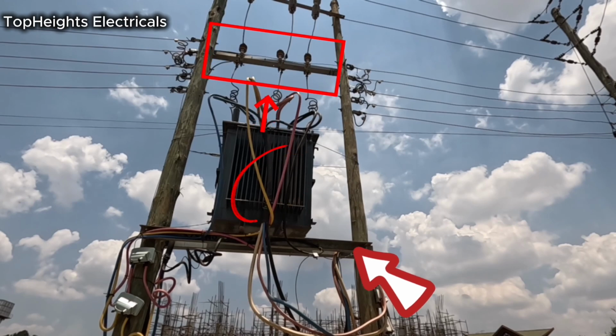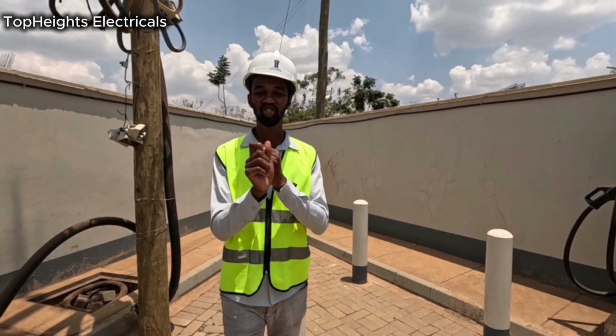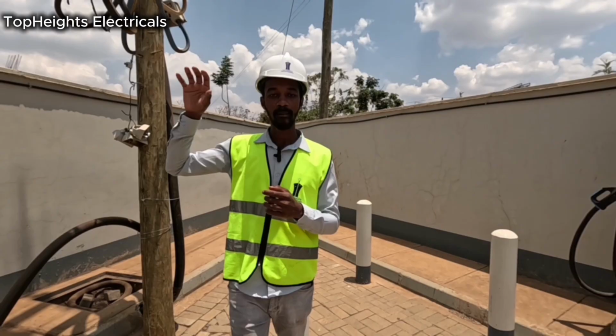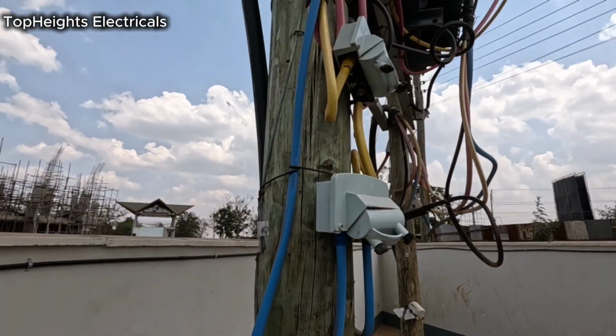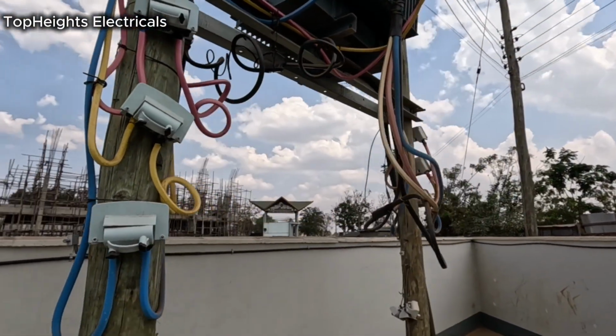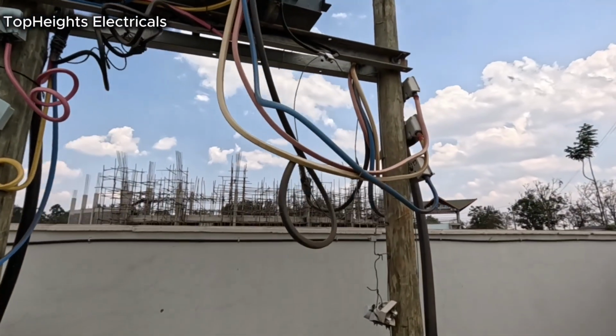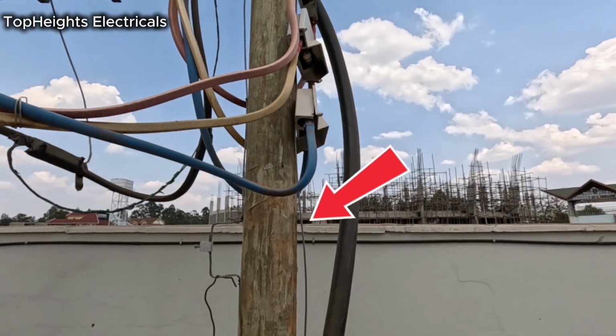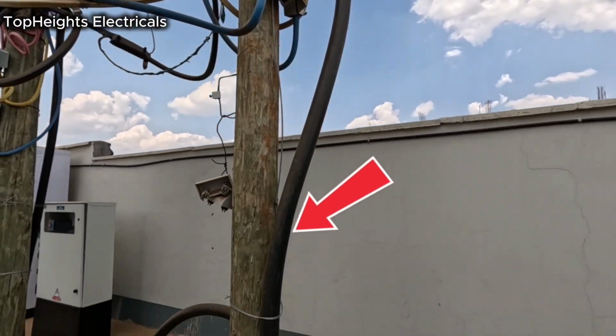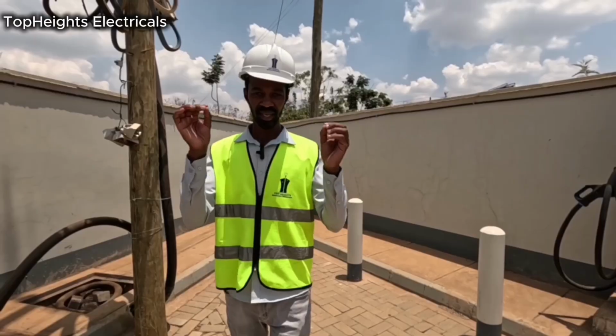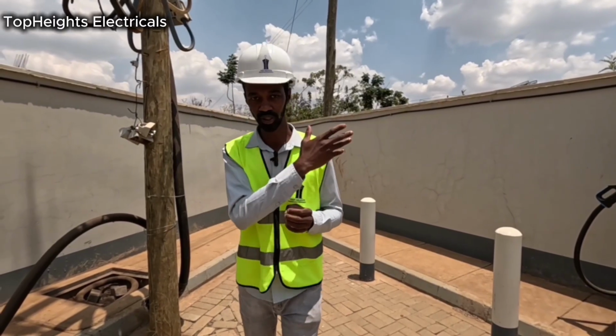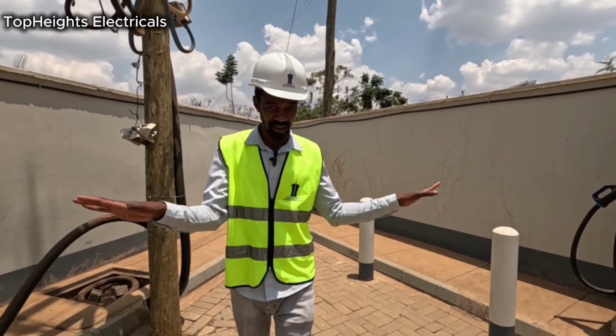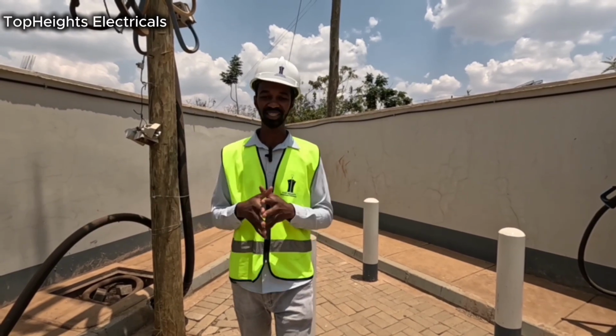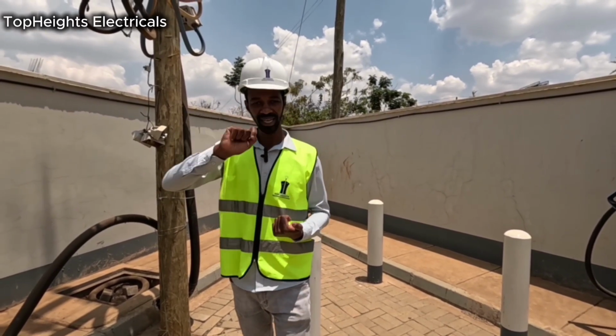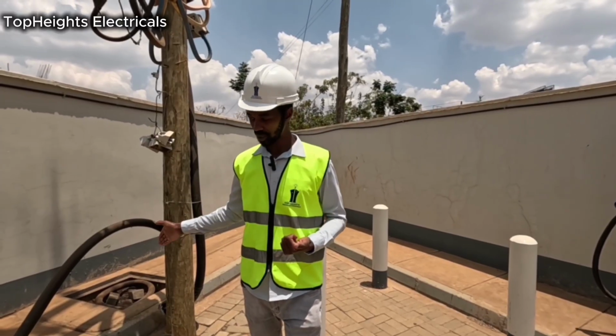Number one, the entire metallic structure is earthed to the ground. Number two, we have the surge protection — if this structure is hit by a power surge, maybe from lightning or any excessive power, it will go to the ground. And number three, very important, is what we call the PME, the protective multiple earthing, connected on the output cables going to the EV charging stations. This ensures that the neutral is connected to that earthing all the way to the ground.